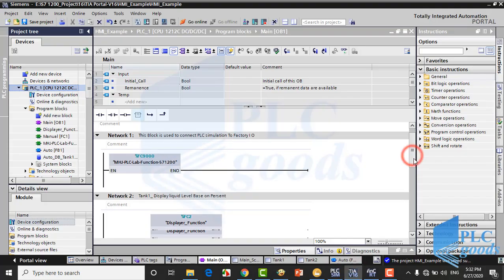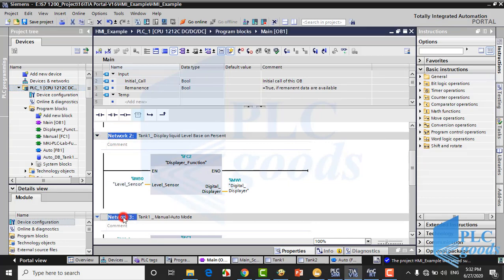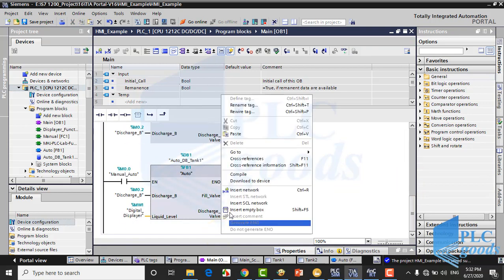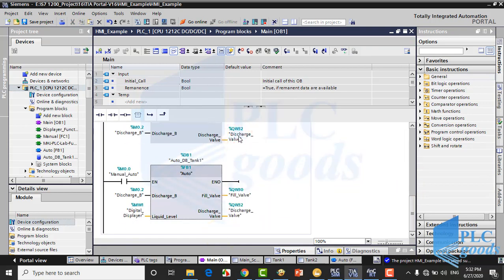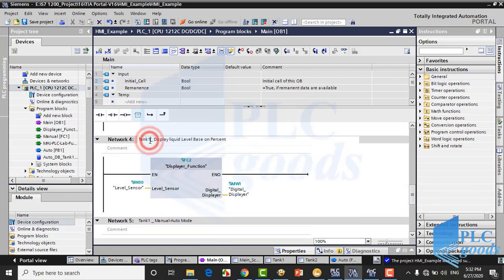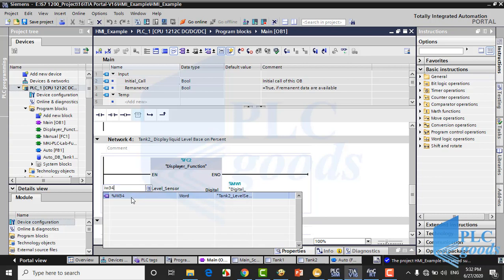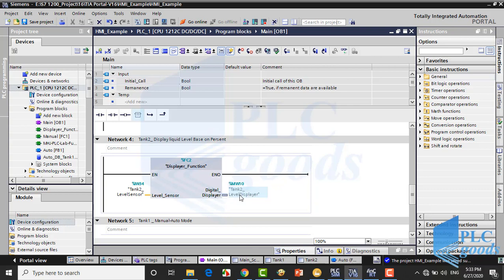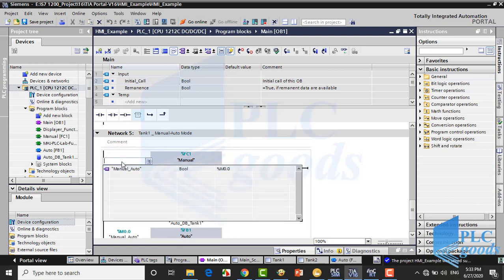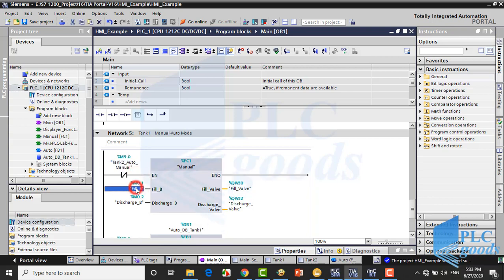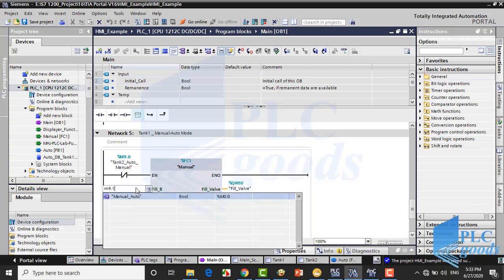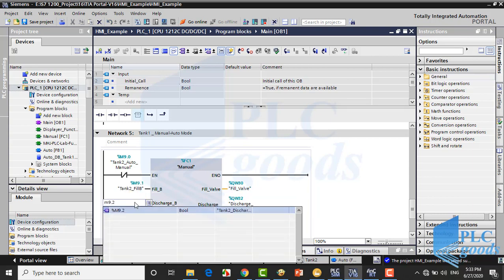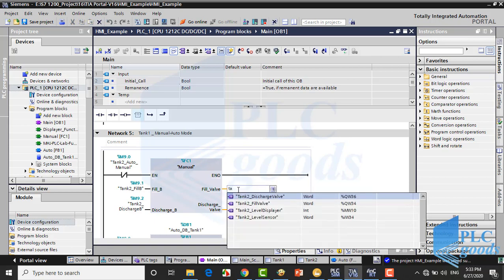To modify the PLC program, we can use previous functions for the new tank, but their input/output must be modified. Here I must change the function input. The second level sensor is connected to IW34. And also I must use another memory to store the liquid level of the second tank. I can enter new addresses or use new tags which I have defined before.